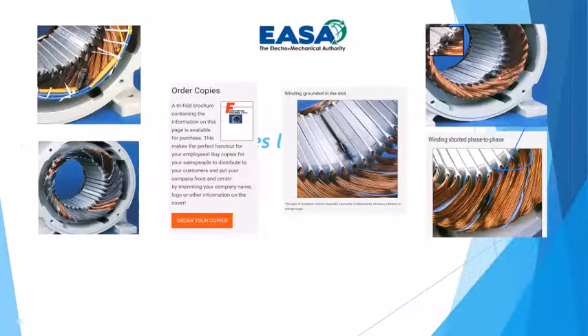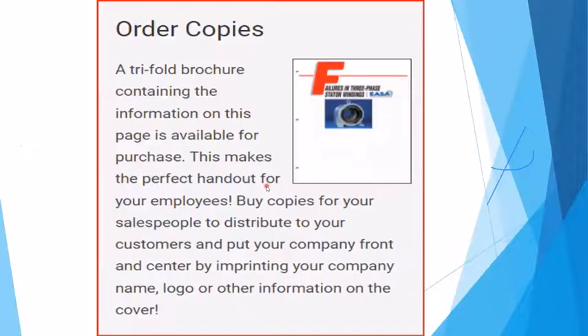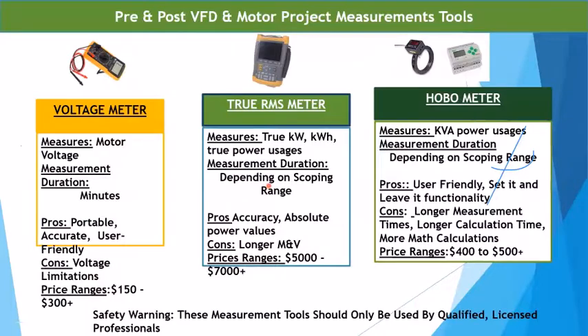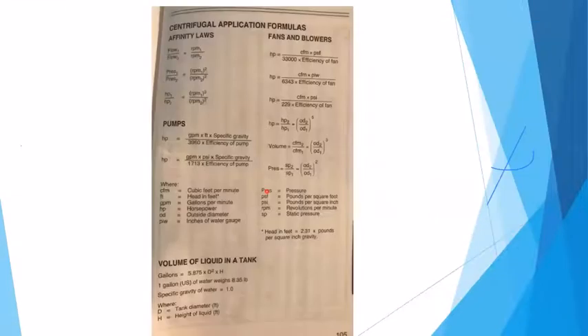This one showed, again, a higher voltage that ended up shorting to ground. And this one shows a higher voltage between phase to phase, and it actually shorted the windings together, so then the motor fails. It has more detail. You can go online and look up EASA. You can easily get access to that.